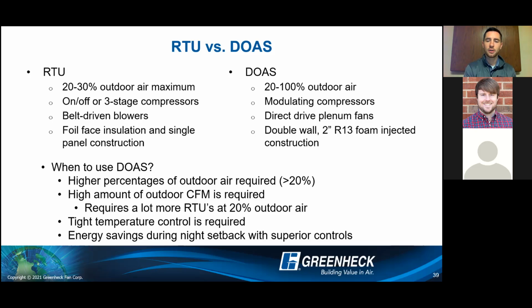Belt-driven blowers on the RTU versus the direct drive plenum fans handling higher statics in the DOAS units. And then from a construction standpoint, seeing foil face insulation, maybe single panel construction with less thermal breaks, less thermal resistance compared to the double-walled 2-inch R13 injected foam that you're seeing on the DOAS side of things. So when to use DOAS?